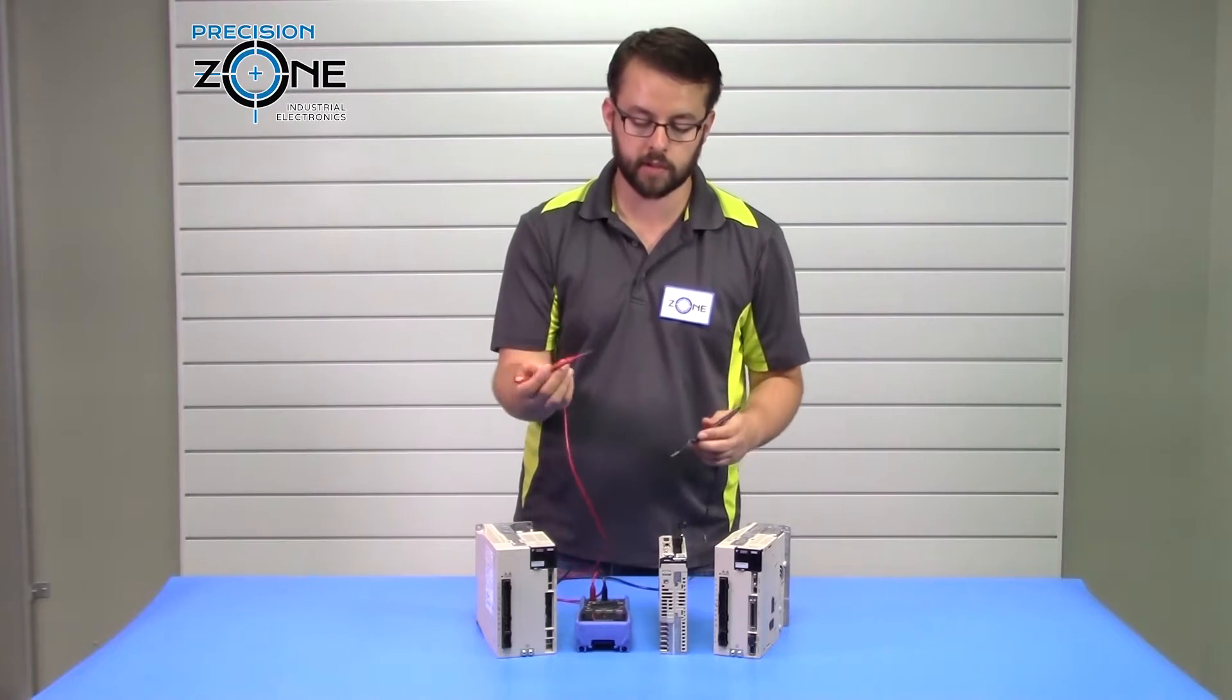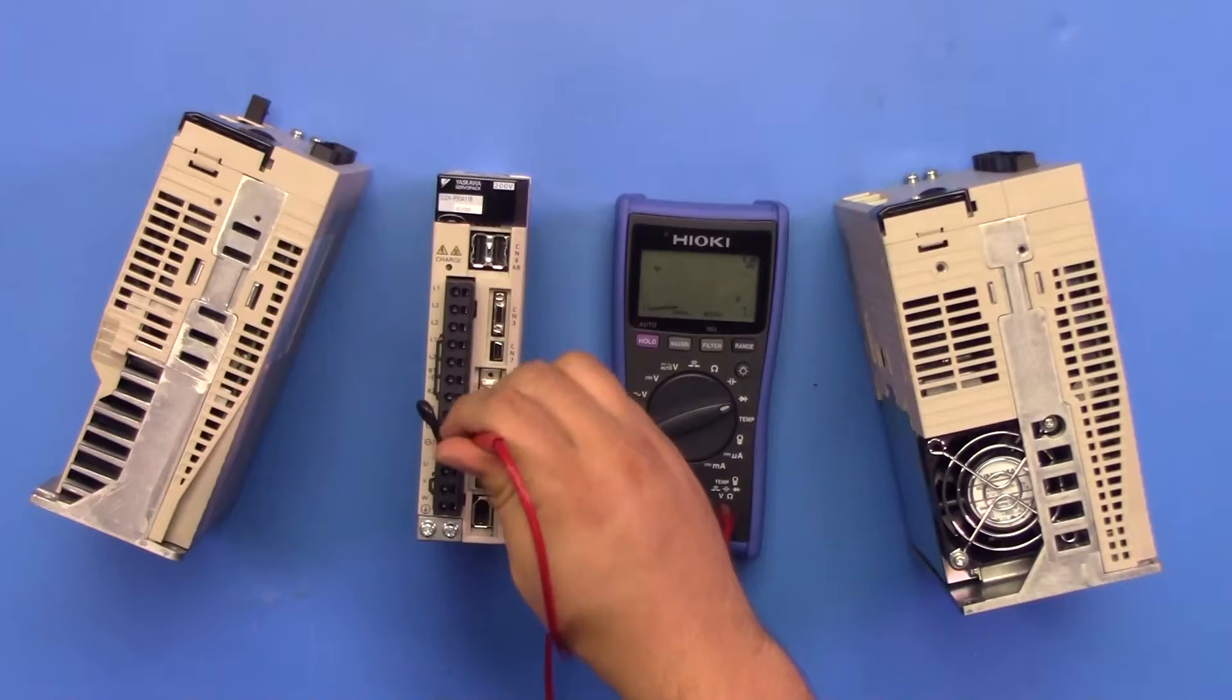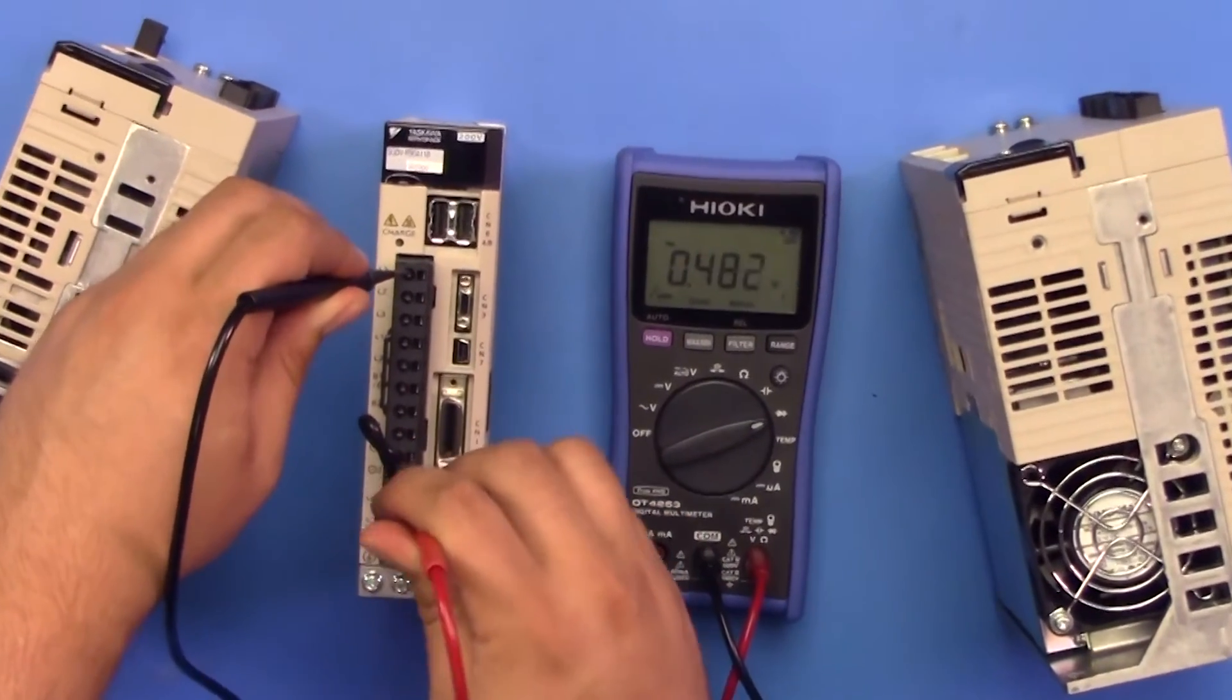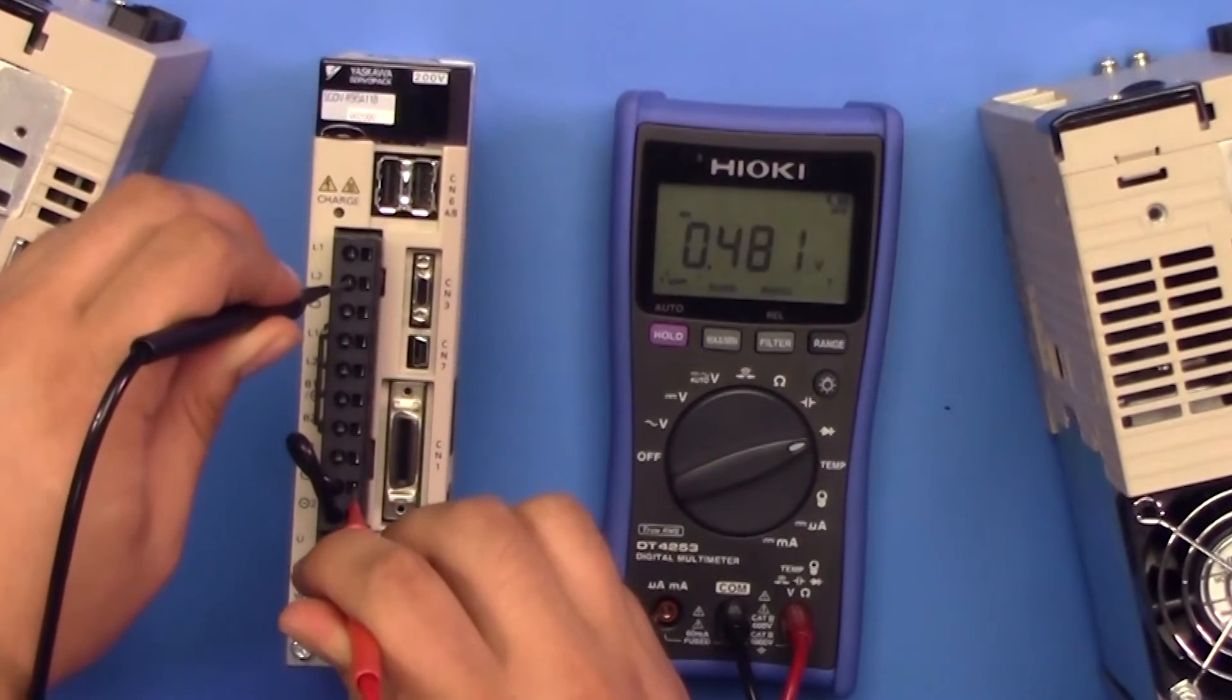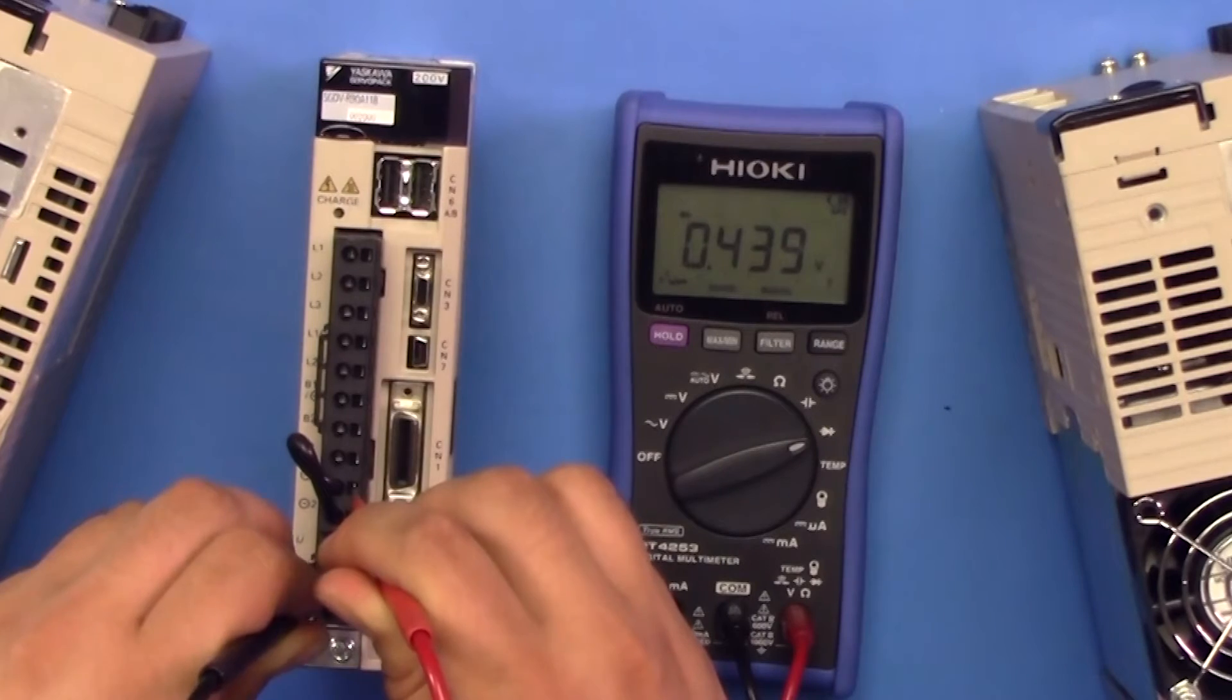Now you're going to want to switch. You're going to use the positive side of the digital multimeter and connect it to the negative side of the DC bus. And you can check your inputs at L1, L2, L3, which is 0.48 volts, and your outputs at UVW, which is about 0.44 volts.